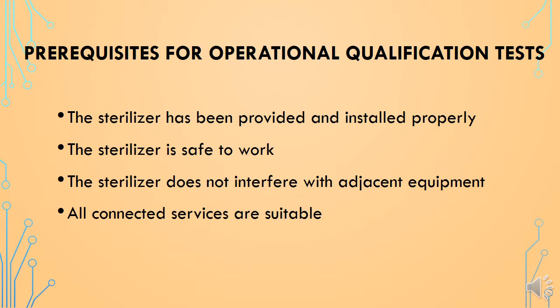There are a few pre-checks or prerequisites for operational qualification tests. These are: the sterilizer has been provided and installed properly, the sterilizer is safe to work, the sterilizer does not interfere with adjacent equipment, and all connected services are suitable.